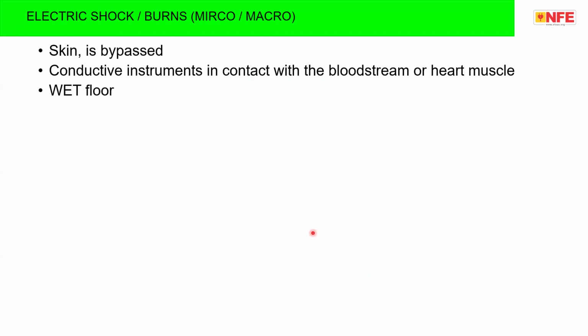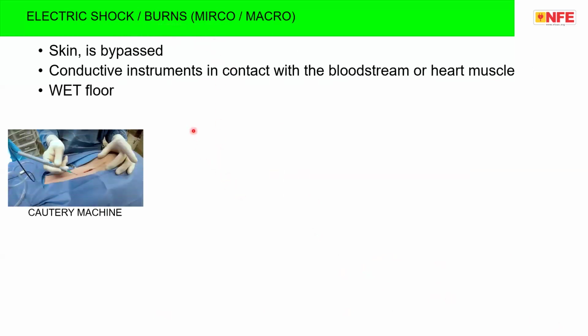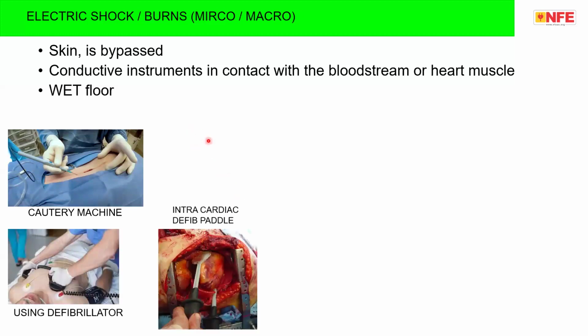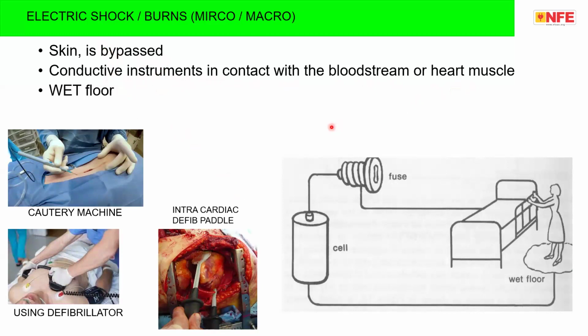Similarly, another subject of equal importance is electric shock from appliances, or burns on a patient's body. We should understand that the medical location is very critical for shock, where the skin is bypassed. Even very small potentials, small energies, can burn tissues, kill people, or cause electrocution. Conductive instruments are in contact with the bloodstream or heart muscles, and the floor is wet. Basically, we are talking about a highly sensitive, electrically dangerous location where such activities are going on.